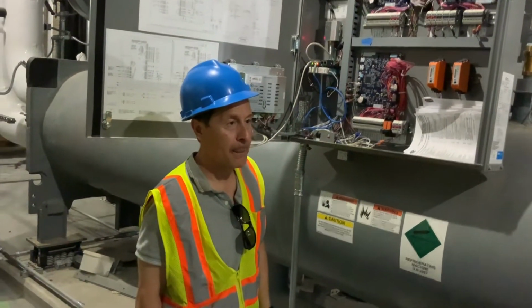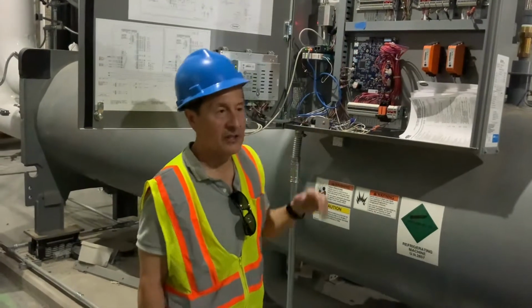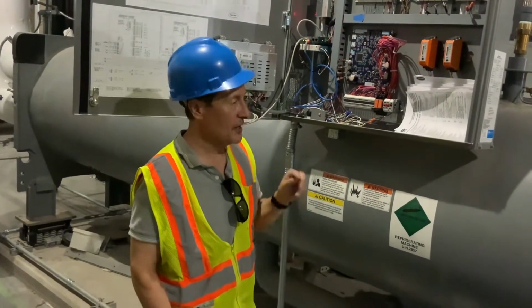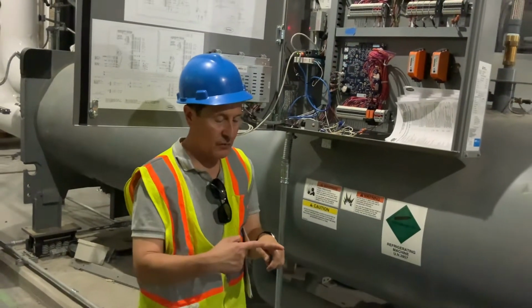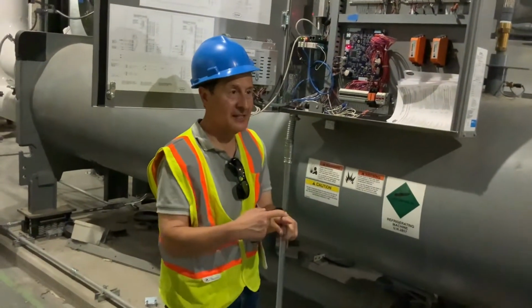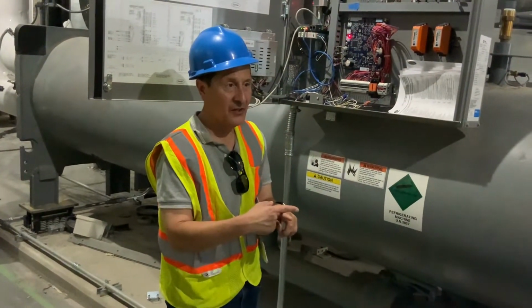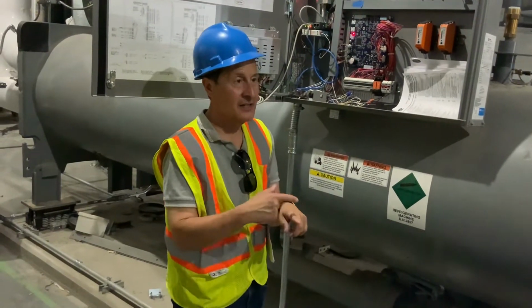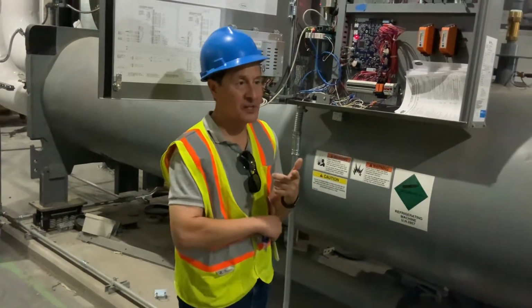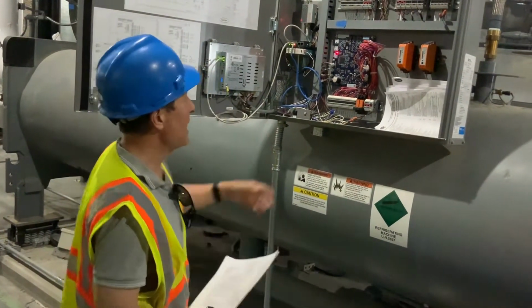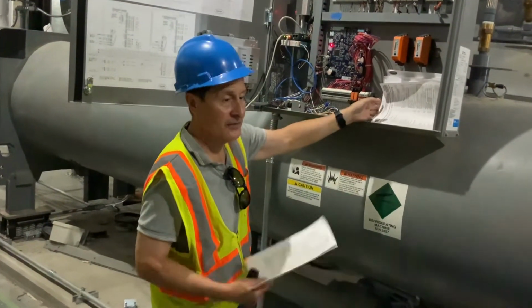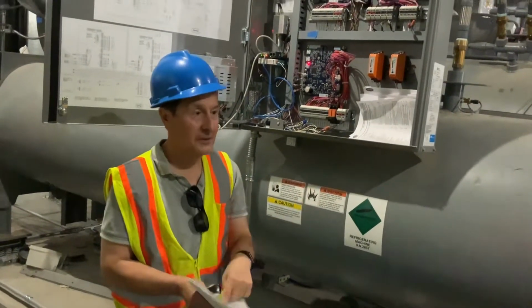The way these work is they're called calorimetric sensors. There's an electronic probe in there, and the speed at which the fluid flows past it dissipates the heat off of the electronic sensor. So the rate of heat dissipation tells it what the velocity is across the flow. Pretty cool stuff. Very reliable sensors. The IOM manuals are in here. I printed these out from the manual, so they have that.